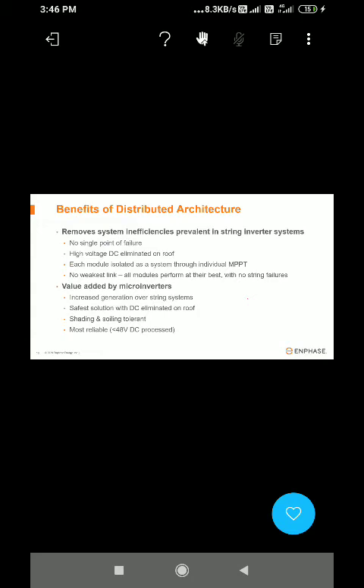What does that mean? Basically, when we have a string inverter or centralized inverter, we have a single point of failure - if the inverter is down, we have a complete shutdown of the solar system. Even if the sun is out, we can't produce because the inverter is out. But with distributed architecture, we do not have a single point of failure - every solar panel is a system. So if one microinverter out of 10 is down, the other 9 are still working and producing.